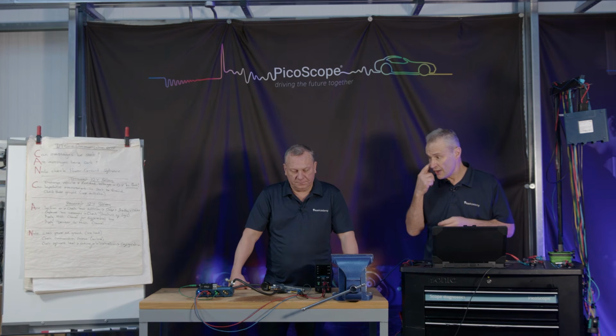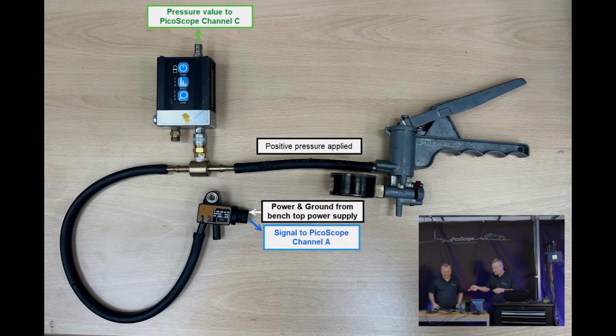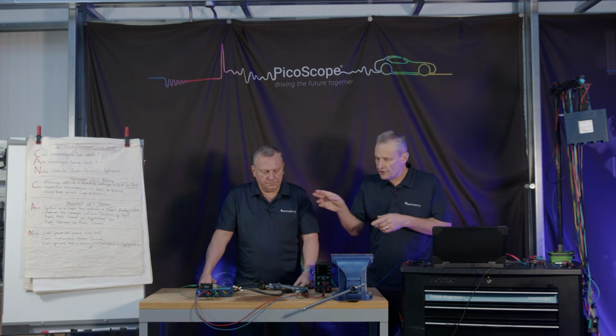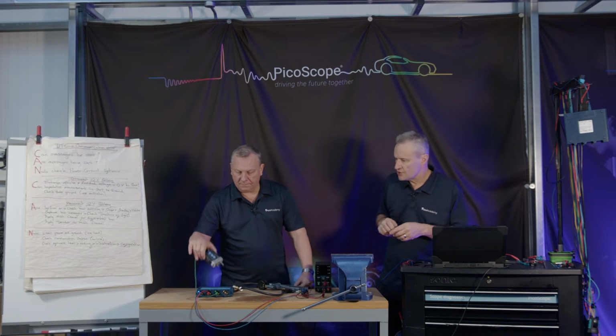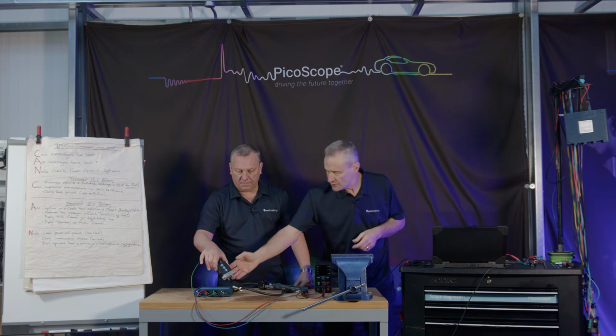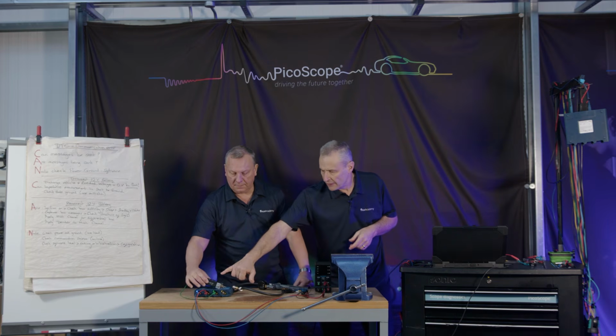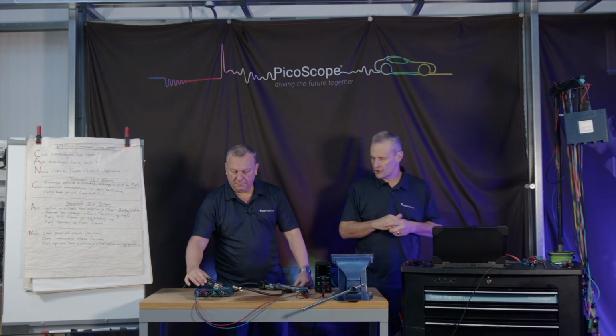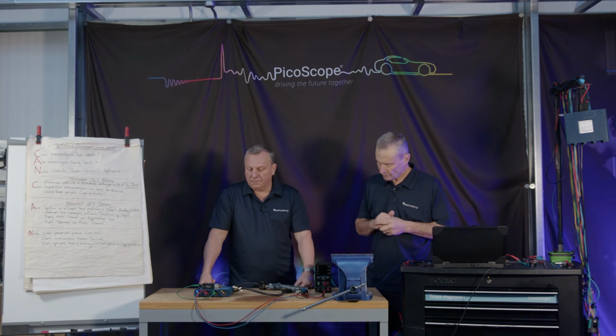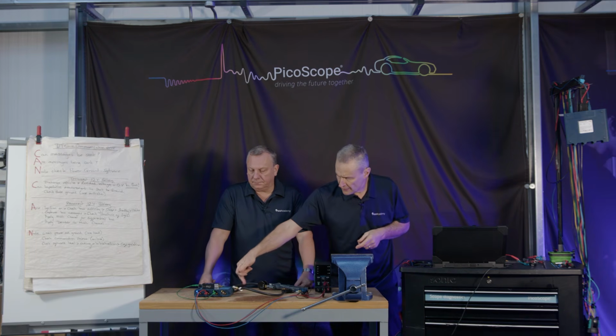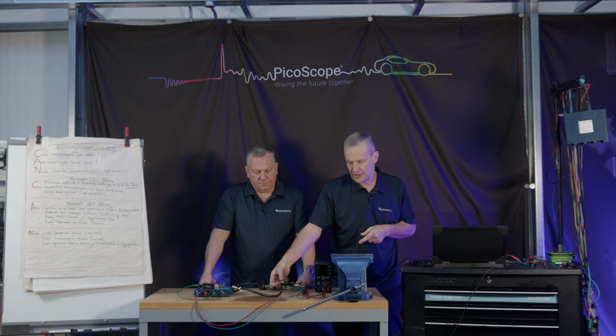So if we just describe the setup, we've got a Mityvac connected to a DPF pressure sensor. This is a Denso device. We are going to apply positive and negative pressure - in fact it doesn't matter which one, we'll go with positive. We'll use the WPS pressure transducer as well. So what we'll do is switch that on and let the power go through each range, 1, 2 and 3, because it's got to calibrate. We'll put this in line with the Mityvac and apply pressure to this sensor.